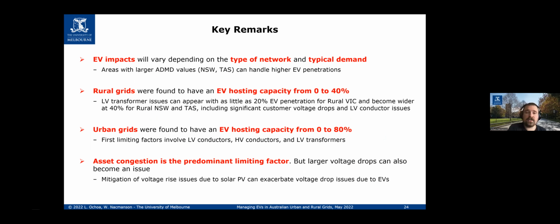In general, EV impacts vary depending on the type of network and the typical demand. If you have a higher ADMD, you can typically handle higher EV penetrations because your networks are built for it, but that can also work against you because you may already have higher existing load. So it's not quite as simple as that—it can work both ways, depending on your network and type of demand.